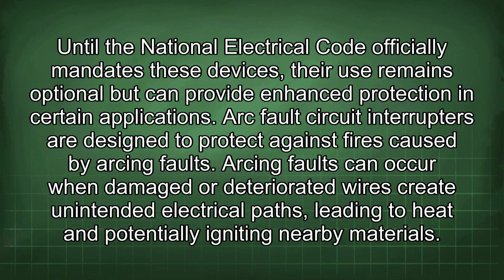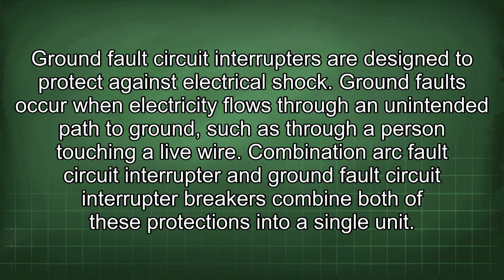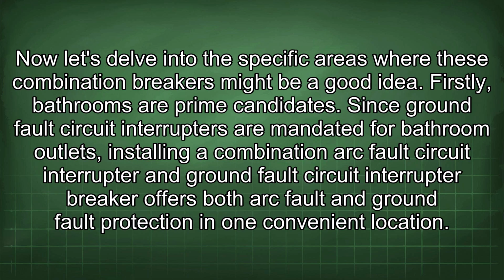Arc fault circuit interrupters are designed to protect against fires caused by arcing faults. Arcing faults can occur when damaged or deteriorated wires create unintended electrical paths, leading to heat and potentially igniting nearby materials. Ground fault circuit interrupters are designed to protect against electrical shock. Ground faults occur where electricity flows through an unintended path to ground, such as through a person touching a live wire. Combination arc fault circuit interrupter and ground fault circuit interrupter breakers combine both of these protections into a single unit. Now let's delve into the specific areas where these combination breakers might be a good idea.